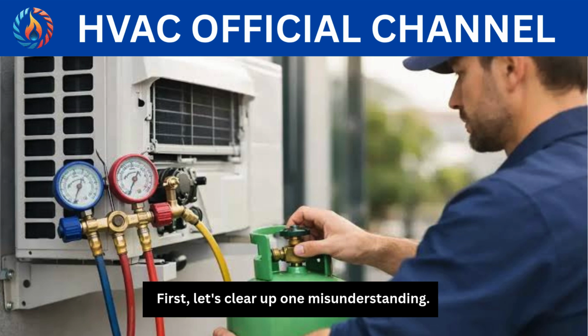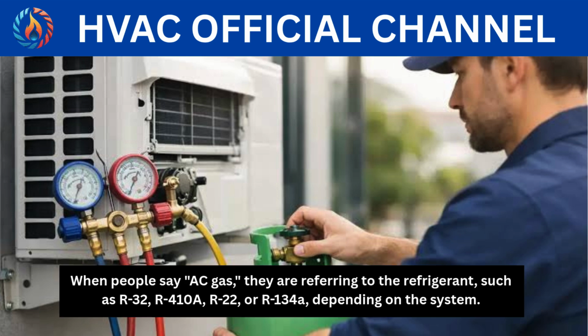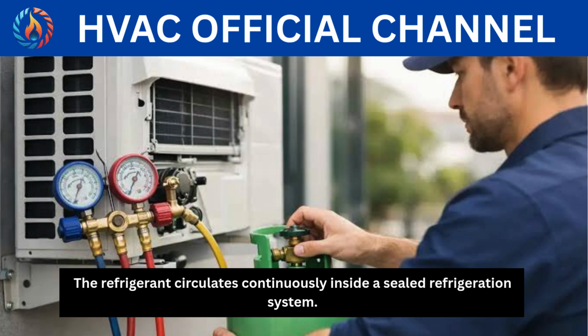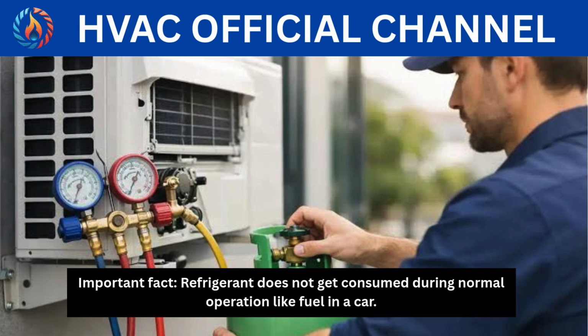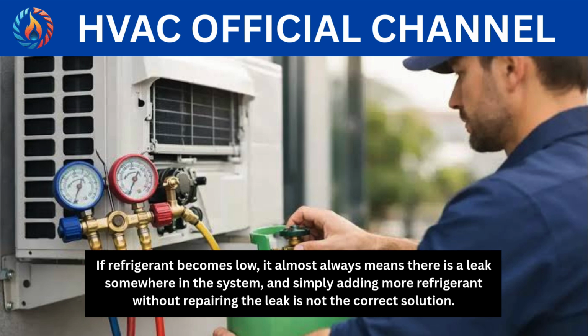First, let's clear up one misunderstanding. When people say AC gas, they are referring to the refrigerant, such as R32, R410A, R22, or R134A depending on the system. The refrigerant circulates continuously inside a sealed refrigeration system. Important fact: refrigerant does not get consumed during normal operation like fuel in a car. If refrigerant becomes low, it almost always means there is a leak somewhere in the system, and simply adding more refrigerant without repairing the leak is not the correct solution.